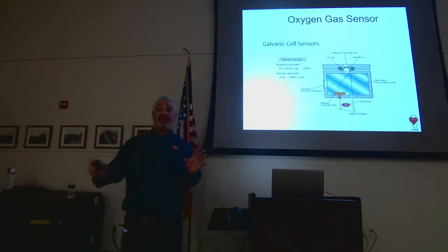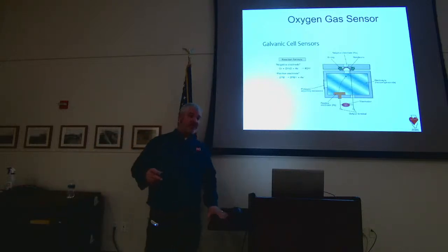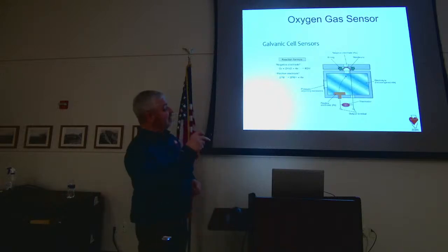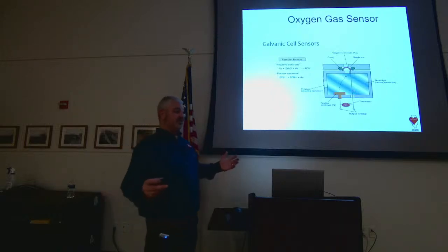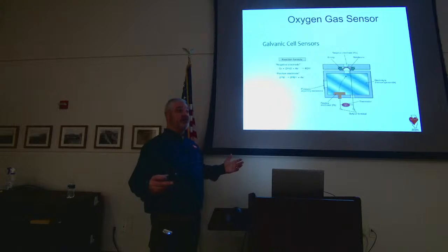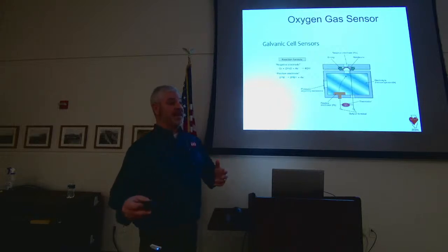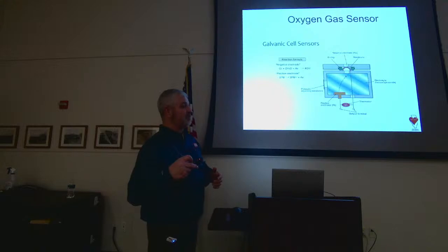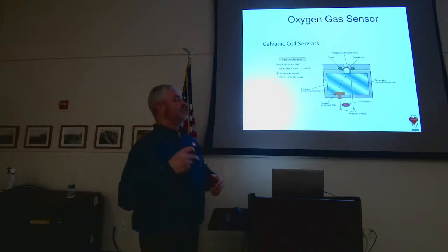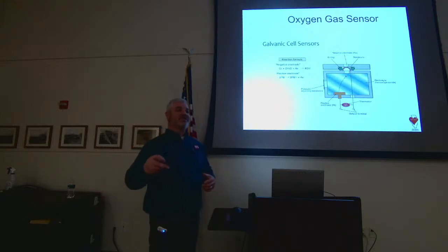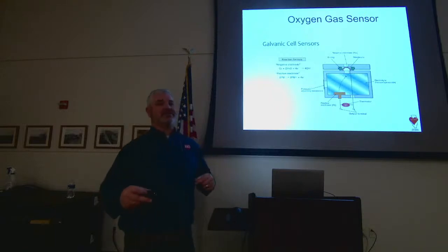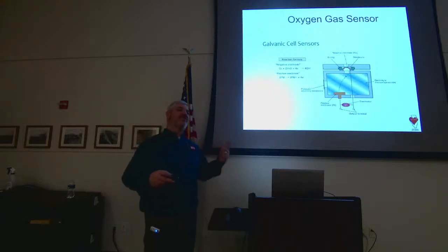That's pretty good, all things considered, because in the old days all people did was complain about their O2 sensors failing. The simple reason was, as soon as the electrolyte is gone, the sensor fails. It has nothing to do with showing it more or less oxygen, because it's always seeing 20.9. So it never stops working, 24/7, 365. Hence, oxygen sensors are most often replaced first.